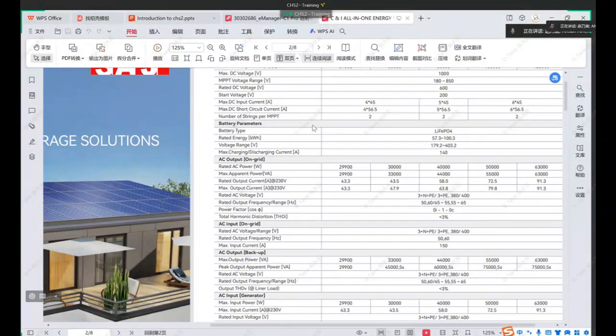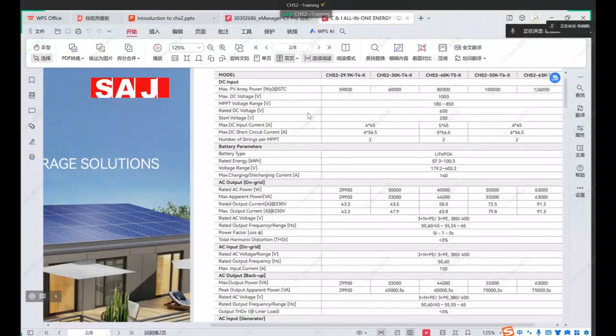Okay, so I have a question. The start voltage is about 200. So if the minimum is 57.3 or 4, but what about if the standard voltage of every battery cell is 3.3 and they have a minimum, that means as soon as the battery capacity becomes lower, the voltage will be lower than 200 volts. Does that cause some problems?